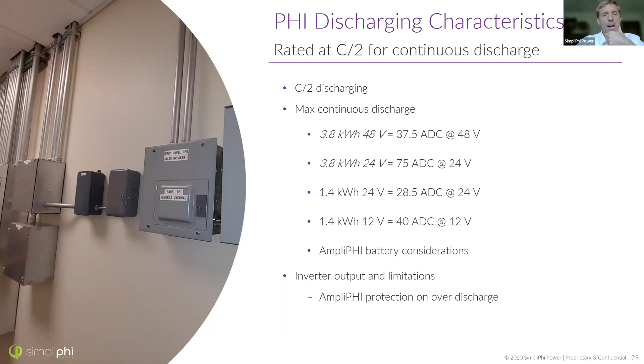As well, you want to make sure that the inverter has the protection for discharge, etc. The AmpliPHI has that kind of built into the battery management system. Okay. So for the Phi Battery discharging characteristics, it's the same kind of thing. These batteries do offer you a surge. So the AmpliPHI will give you 100 amps for a surge for 10 minutes. It's perfectly fine to discharge at this high rate. It's a little bit above C, but for a short amount of time.